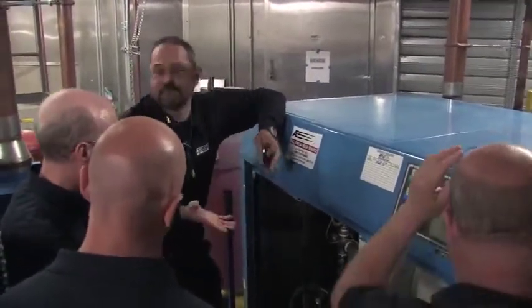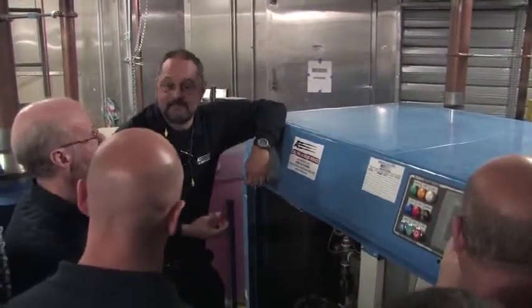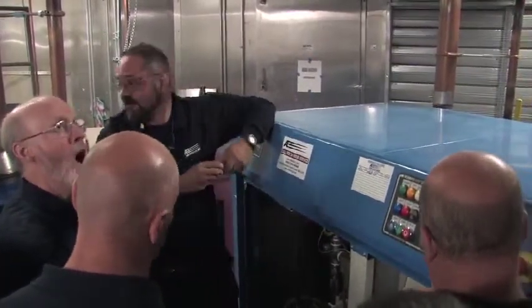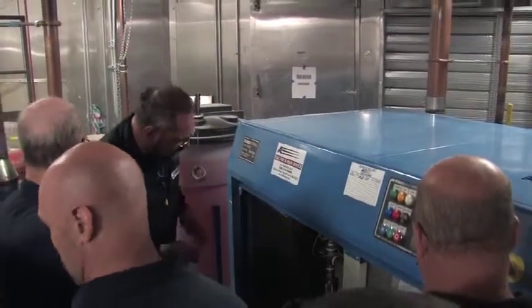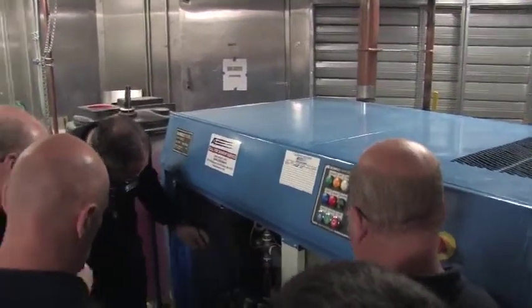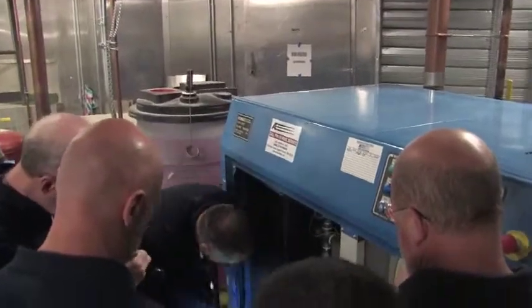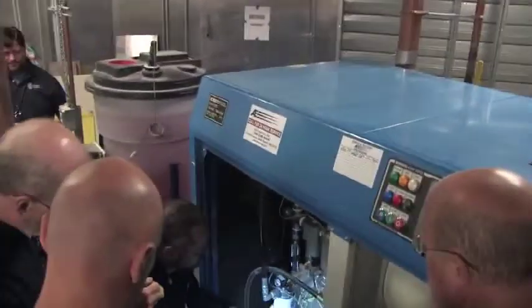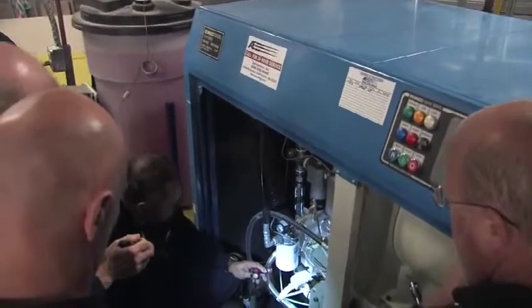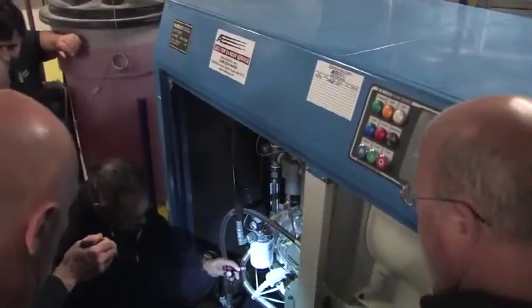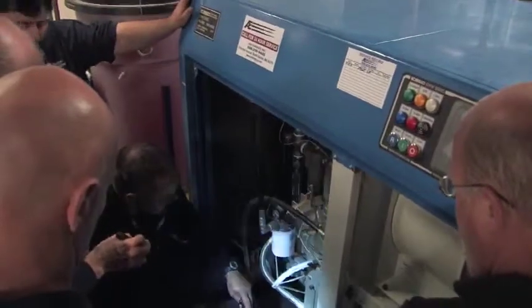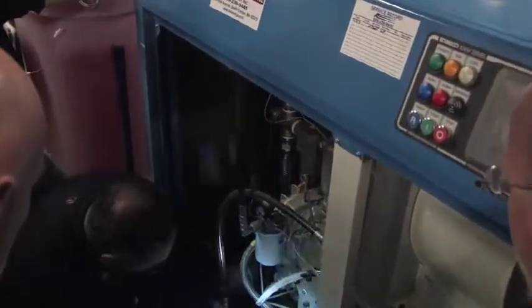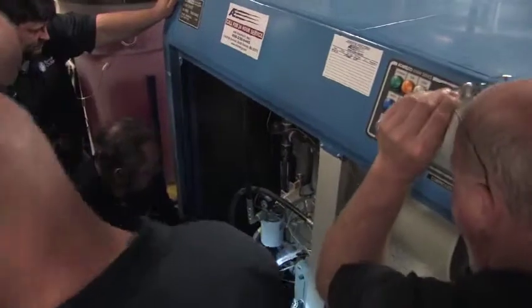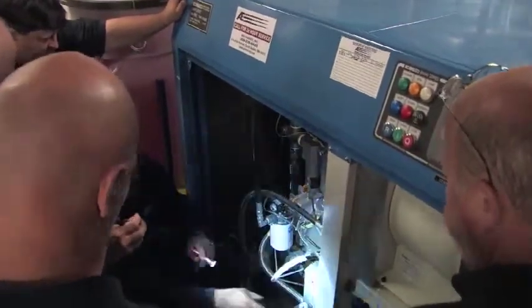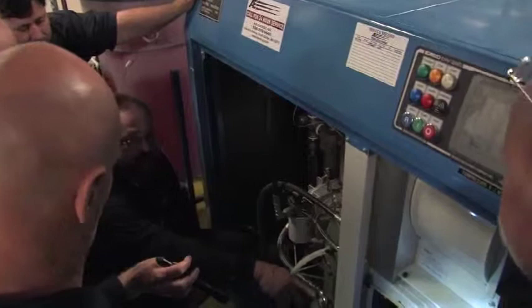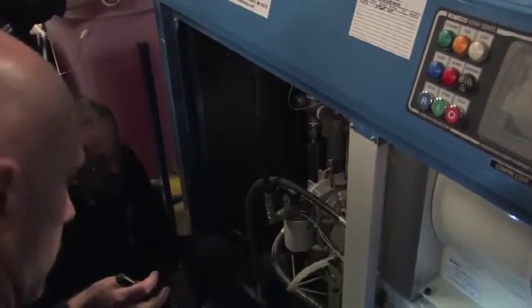And if you take it down and the filter is absolutely clean, then did a bird build a nest? Especially if all three of them are doing it. Did something finally figure out a way to nest? So our air is coming in here, going down through the intake valve. Those of you who've played with these machines before know that annual maintenance consists of changing the oil. Oil fills here, drain is on the far side. Changing the oil filter, replacing the load solenoid, which in this unit is mounted back there, a lot easier to get to than on the old ones.